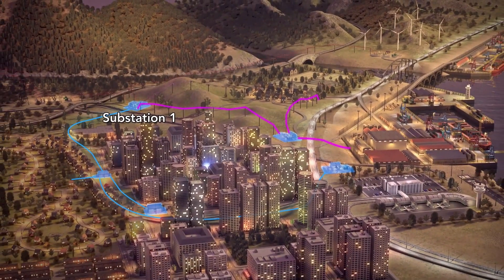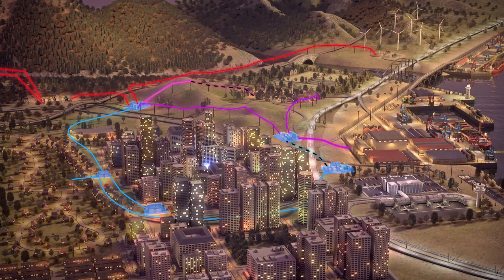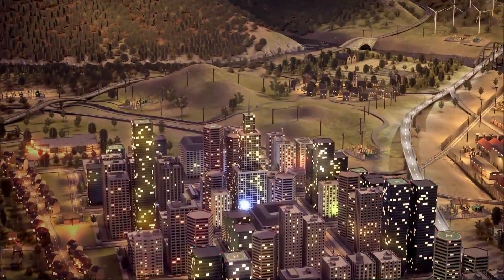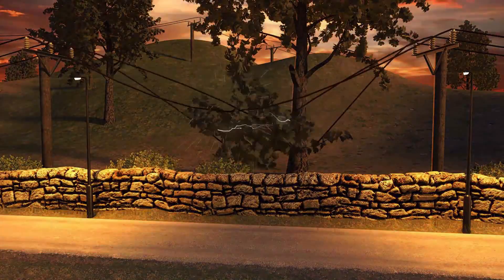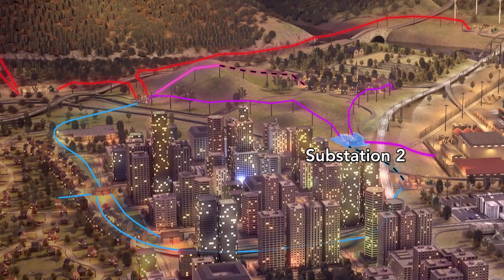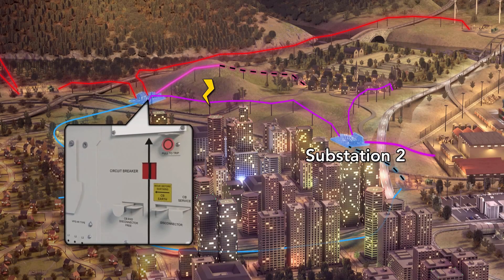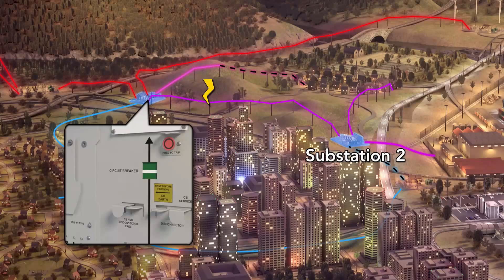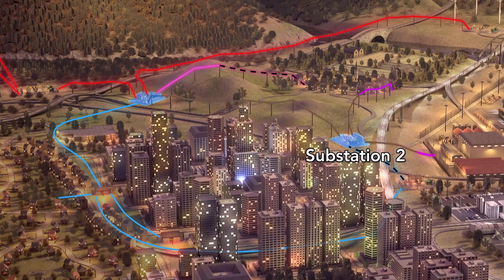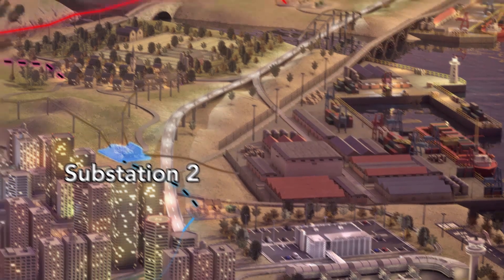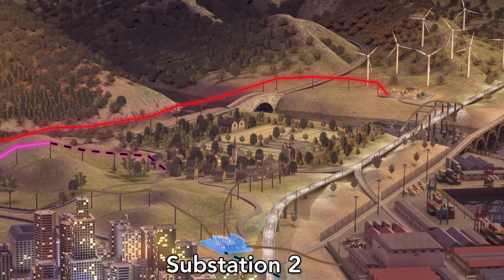Let's see how the SCADA system is used to manage and maintain the network during a fault. On a remote rural section of the network, a fallen branch causes damage to the overhead power lines feeding substation 2. This break in supply causes the circuit breaker for this line to trip at the primary substation, leading to a total power outage to both the port and the rural community that rely on this circuit.